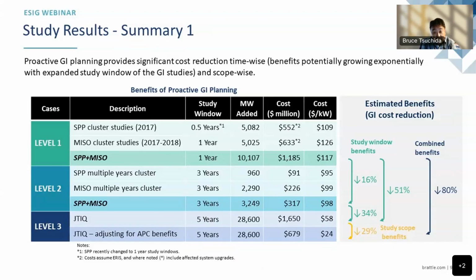Between level 1 and level 2, just by expanding the scope of the cluster studies, you're seeing a 16% cost reduction, from on average $117 per kW to $98 or less than $100 per kW. Now if you look at the JTIQ study, which looks at 5-year studies, it has a $1.6 billion investment that enabled 28.6 gigawatts, which reduces the average dollar per kW GI cost down to $60. So you're seeing another 33% reduction compared to level 1. It's effectively halving the cost.